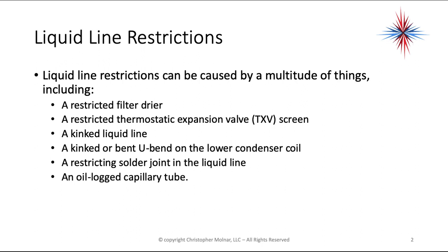These causes include a restricted filter dryer — the easiest one to find — a restricted thermostatic expansion valve screen, a kinked liquid line, a kinked U-bend in the lower condenser coil, a restricting solder joint in the liquid line, or an oil-clogged capillary tube.